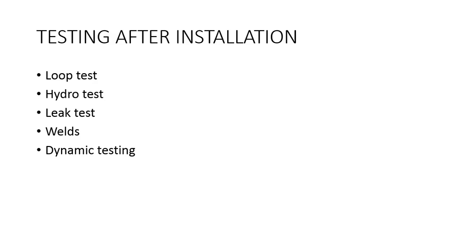Last is the dynamic testing. In dynamic testing, the user must determine how fast and how well the control valve shall respond to the input signal. Also, the valve characteristic is reported in this dynamic testing. Parameters like backlash, time constant, dead band, dead time, dead zone, dynamic response, hunting, overshoot, resolution, response, gain, etc. are obtained and studied further.